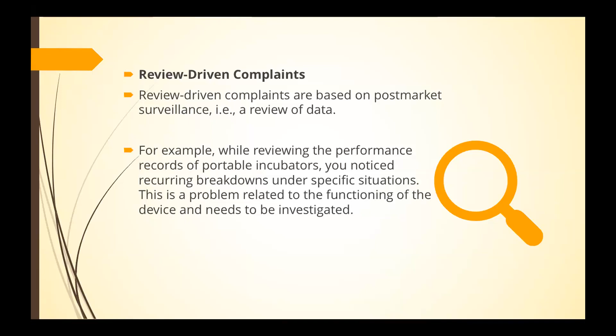So for example, while reviewing the performance records of a portable incubator, you noticed a recurring breakdown under a specific situation. This problem needs an investigation, to understand how it is related to the functioning of the device. So this is basically an example of a review-driven complaint. It does not require immediate attention, but it adds up to the data that we have for a particular device, and it leads back to the trend reporting that we will discuss in the later slides. So this was about incident-driven and review-driven complaints.